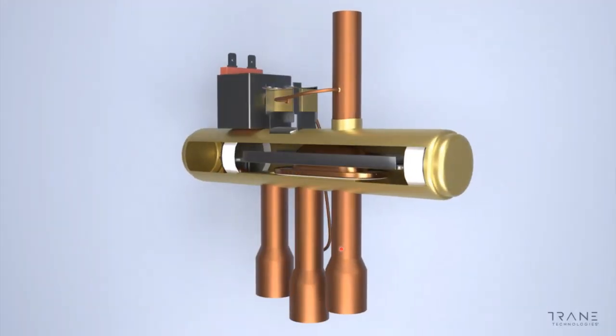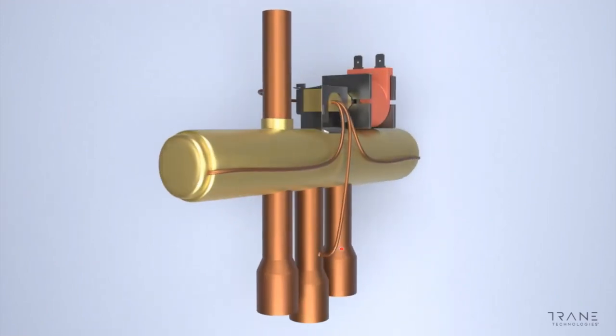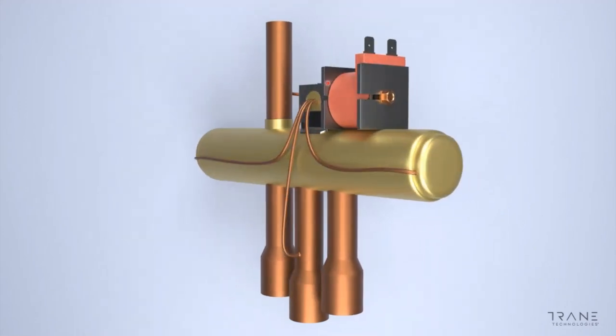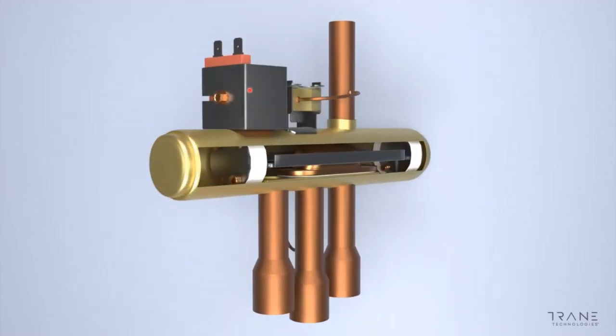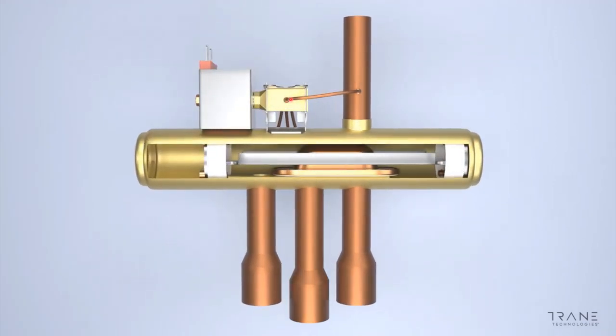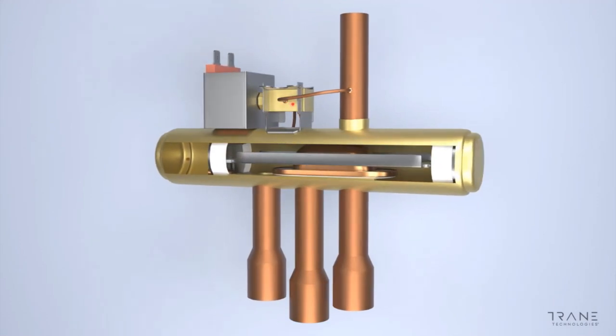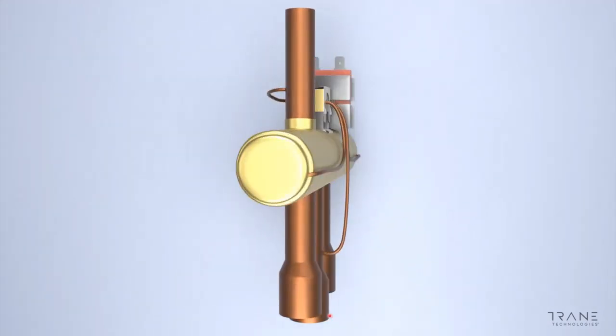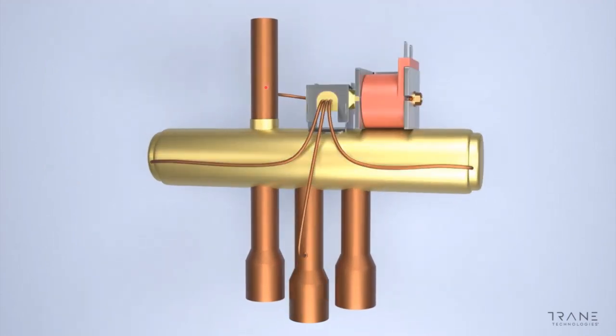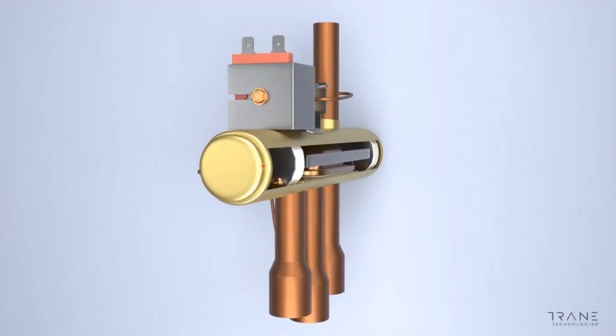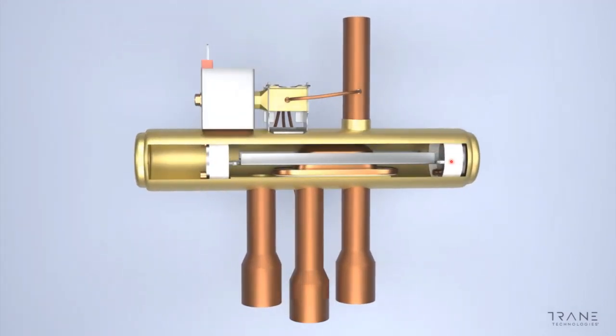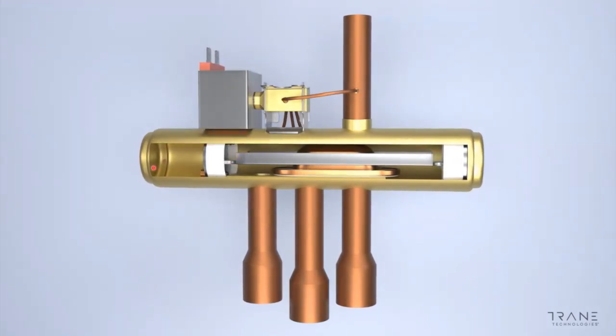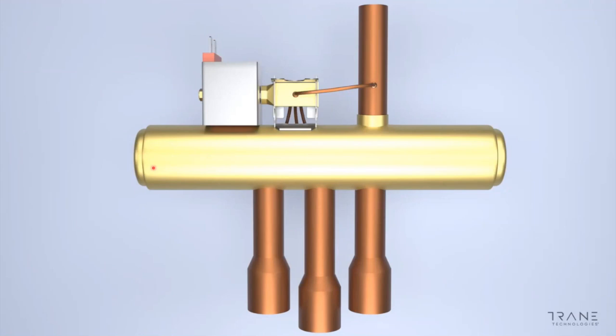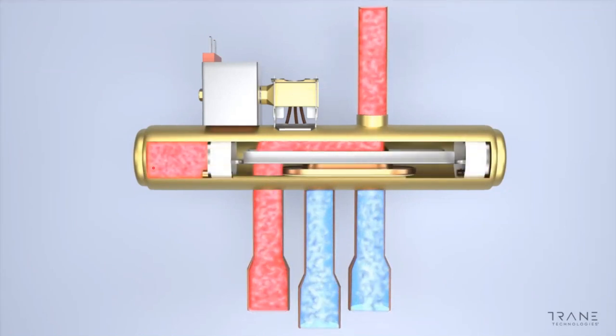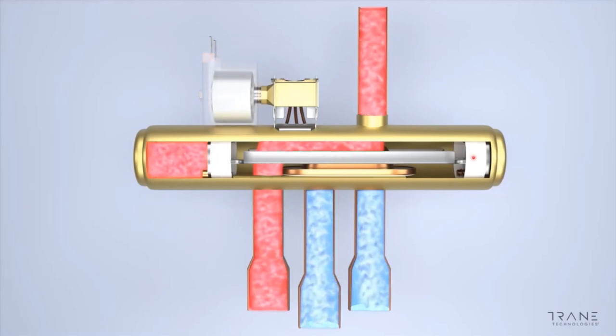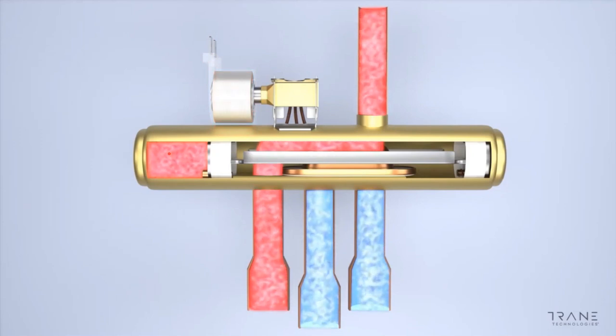So here's a reversing valve, the inner workings of the reversing valve. You can see that this solenoid where your O is hooked up to, all it does is change refrigerant flow in this valve right here. And then it takes and it'll route your discharge pressure to one side of this and your suction pressure to the other side. So it moves this shuttle back and forth. So you do need to have a delta from your discharge to your suction in order to move this shuttle over to change your flow of refrigerant.